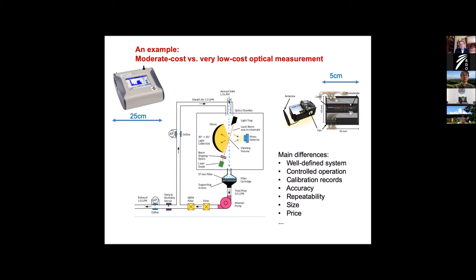Now, what are the basic types of low-cost sensors? There are two. The upper row here shows you the so-called nephelometric measurement. We have here a light source and a photo detection unit. Particles are moving through a volume, and when they are moving through the beam of light, they scatter some light, and this is the only signal which we have. It is a signal from many particles at the same time.